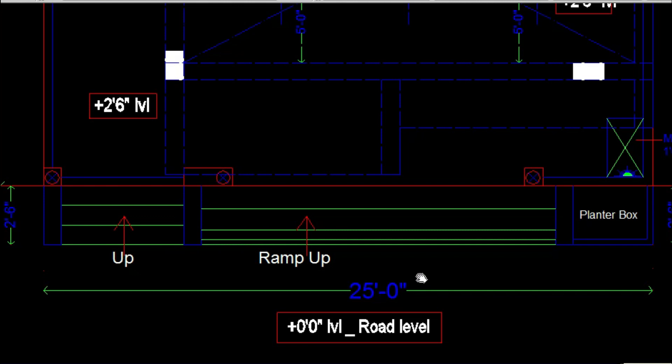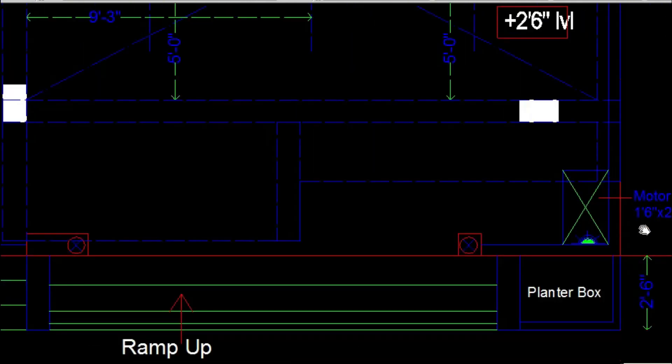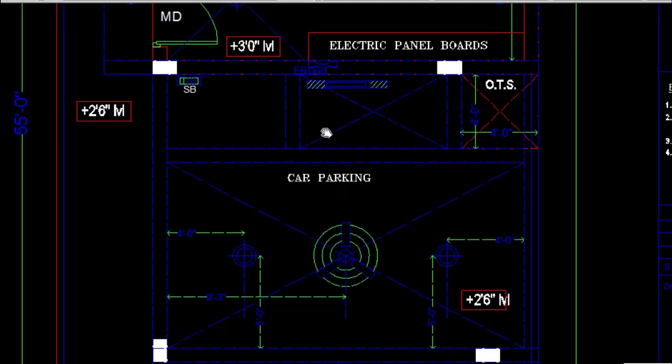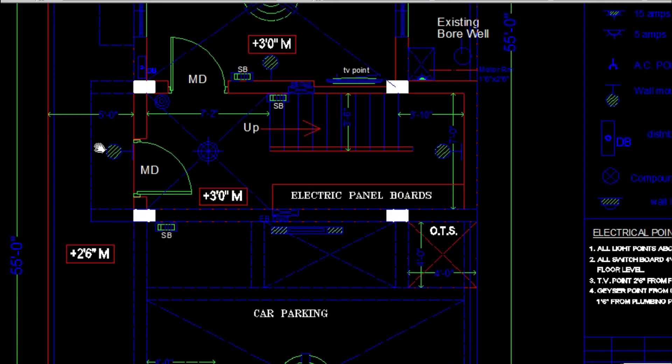Now we are looking at the stilt or ground floor plan. At the corridor, corridor lights are marked over the pillars. In the setback area you can see the motor room which has a 15 amp switch and 15 amp socket. In the car parking you will have to provide a fan point centered between the beams, and on both sides one ceiling light. Tube lights can also be provided on the wall. Switchboards are usually given on the wall side.